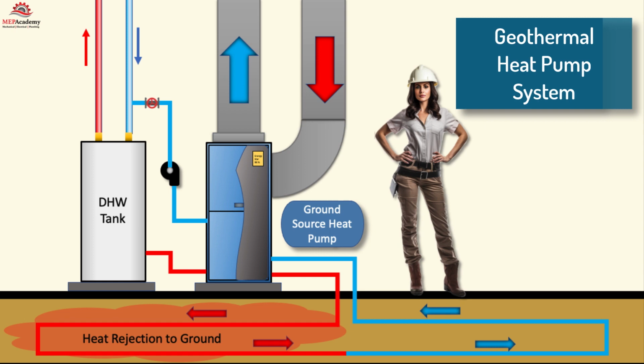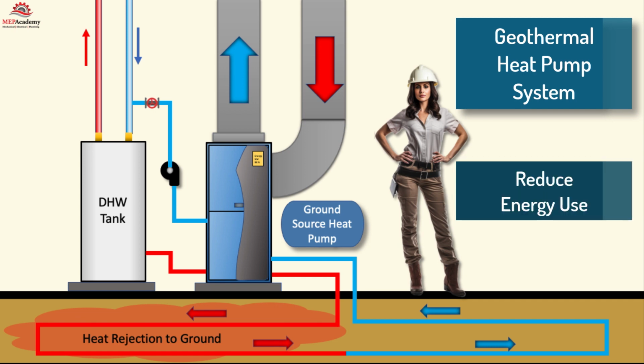By using the excess heat from the geothermal heat pump's cooling cycle, the desuperheater provides a supplemental source of hot water. This can significantly reduce the energy consumption associated with heating water separately.